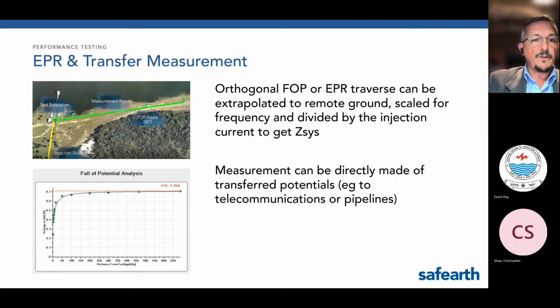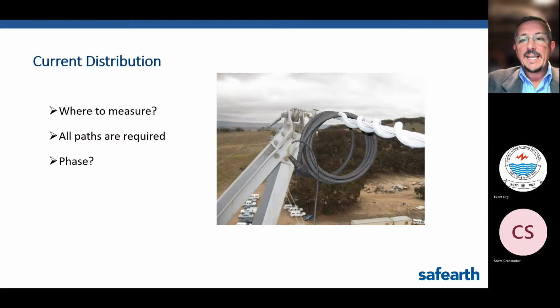We can also measure transfer voltages, say to pipeline assets or telecommunication assets or anywhere else where we're trying to prove that our voltage rise has lowered to an appropriate level by the time it gets to those assets. It's not necessary to measure the current distributions to determine the EPR or to measure step and touch voltages, but it is if you want to determine the grid resistance or the other component impedances.